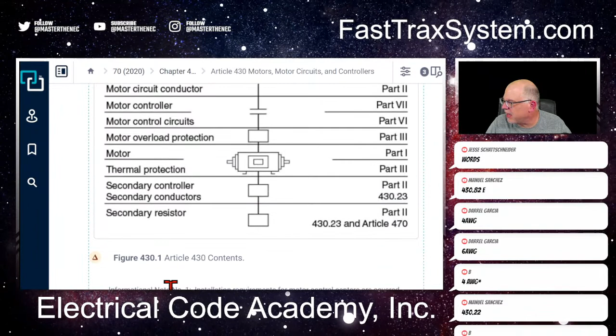So we're back up here at our part references, which is important too. It looks like we have adjustable speed drive systems, 430.120 through 430.131. That's not a lot. For me, I'm stopping right there. Now I could go to the index and look up adjustable speed drive systems or variable frequency drive, and spend a lot of time in the back, but for a motor question like this, I'm better off narrowing it down to a specific area and then bold scanning.